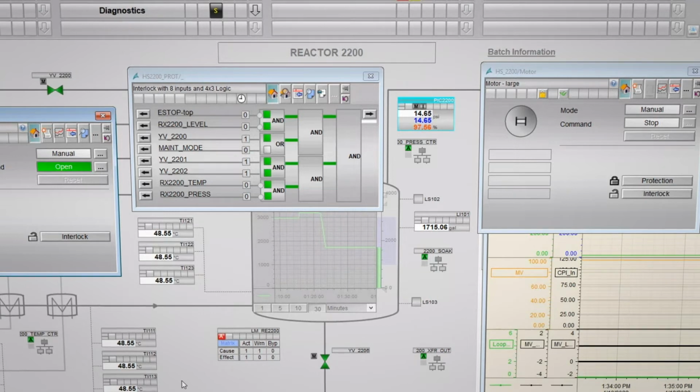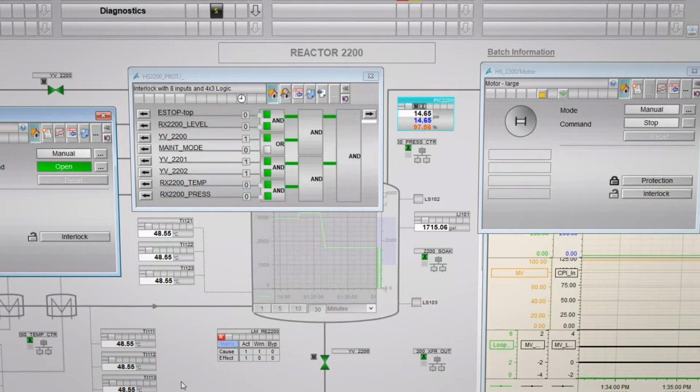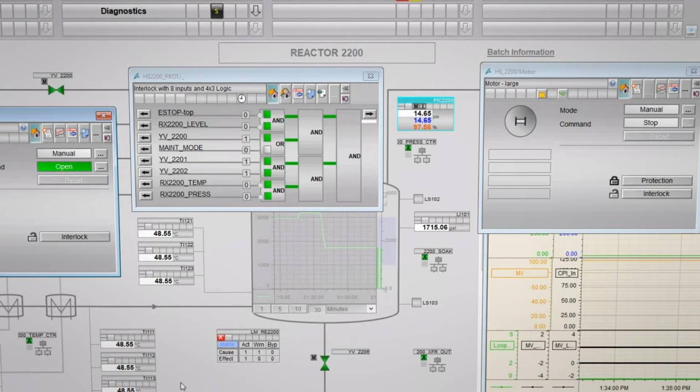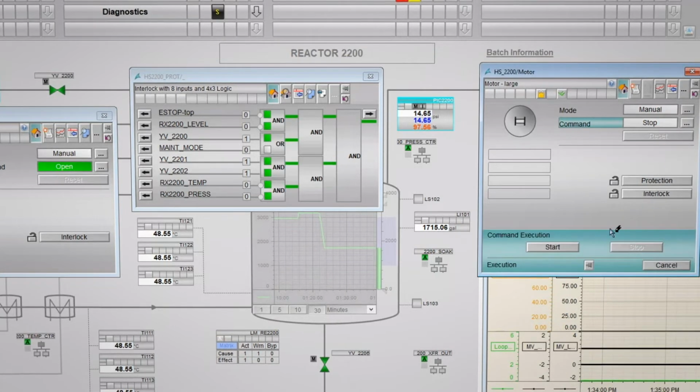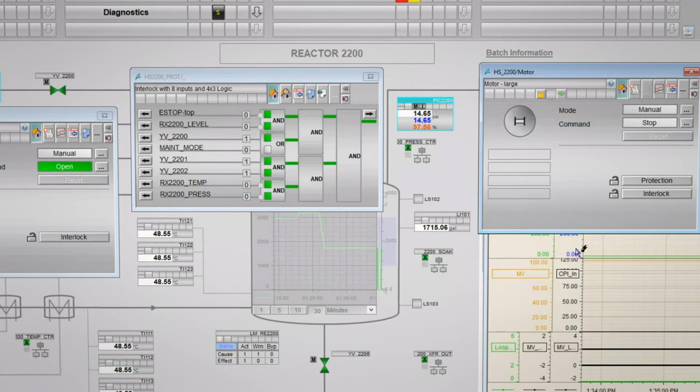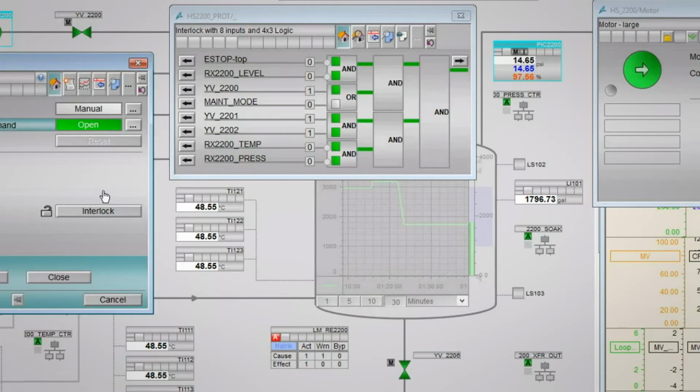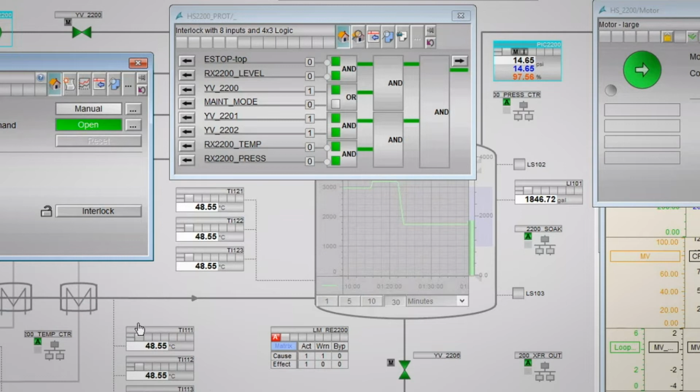The 4x3 function block supports a number of timing operations, such as delay on, off, and pulse functions. Opening the valve allows the pump to start after the pre-engineered delay time. When a trip occurs, the 4x3 captures the first in, crucial in determining which condition failed first. Operators so authorized can clear the first in from the extended faceplate.